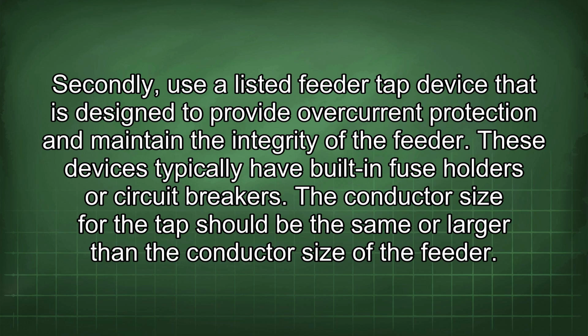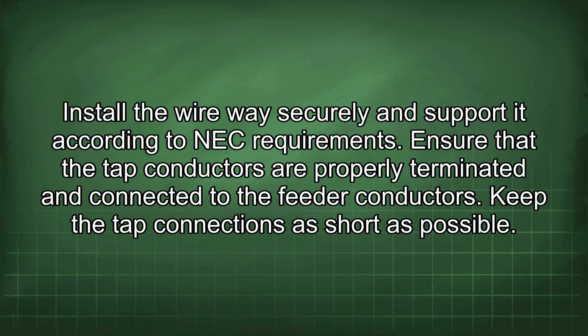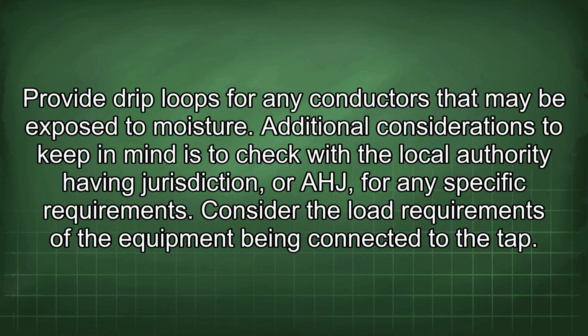The conductor size for the tap should be the same or larger than the conductor size of the feeder. Install the wireway securely and support it according to NEC requirements. Ensure that the tap conductors are properly terminated and connected to the feeder conductors. Keep the tap connections as short as possible. Provide drip loops for any conductors that may be exposed to moisture.